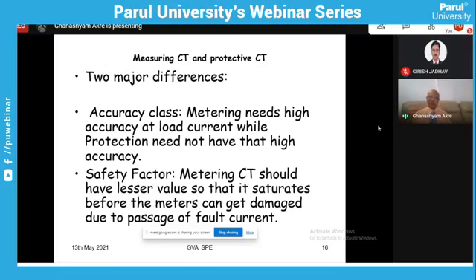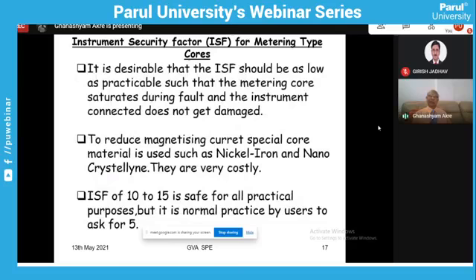And that is why the core of the metering class will always have less area, so that when the current flows more than 3 times, 4 times, or 5 times, the core will saturate and it will not increase the secondary current beyond a certain level, and it will protect the meters. That is how the term instrument security factor has come into the CT. It is generally 5. The standard wants it always 5. 5 means when the current in the primary increases 5 times, the secondary should not carry 5 amperes but less than that. By formula or by definition, it should not be more than 4.5 amperes. So this comes to 4.5, that means your saturation has now started.